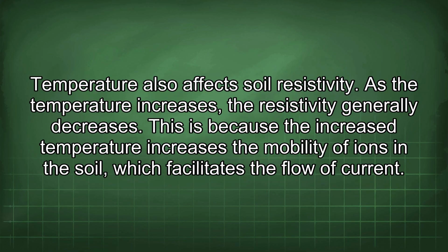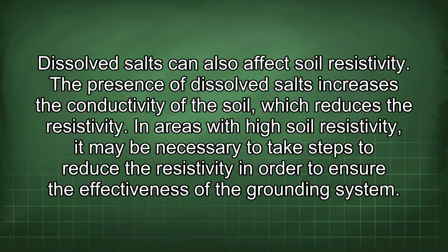Temperature also affects soil resistivity. As the temperature increases, the resistivity generally decreases. This is because the increased temperature increases the mobility of ions in the soil, which facilitates the flow of current. Dissolved salts can also affect soil resistivity. The presence of dissolved salts increases the conductivity of the soil, which reduces the resistivity.